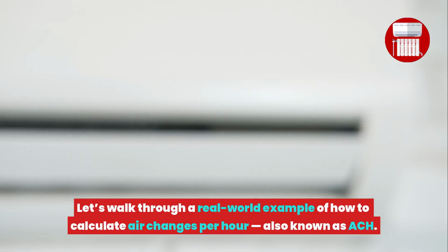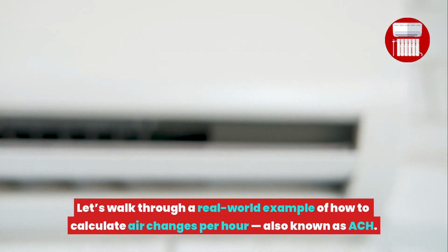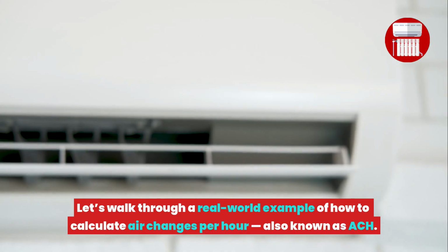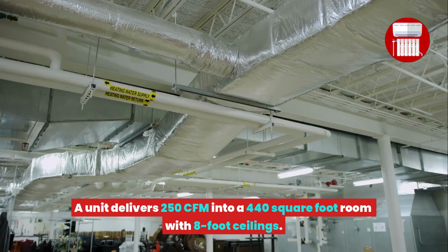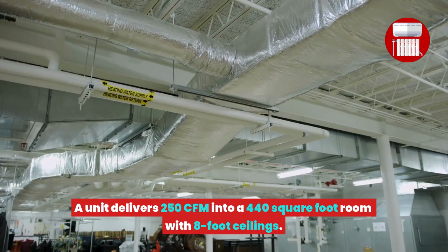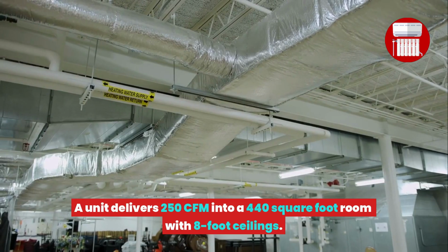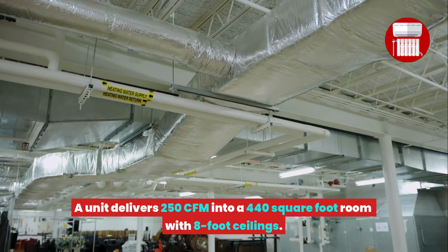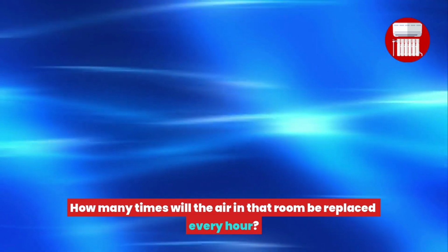Let's walk through a real-world example of how to calculate air changes per hour, also known as ACH. The problem: a unit delivers 250 CFM into a 440 square foot room with 8-foot ceilings. How many times will the air in that room be replaced every hour?